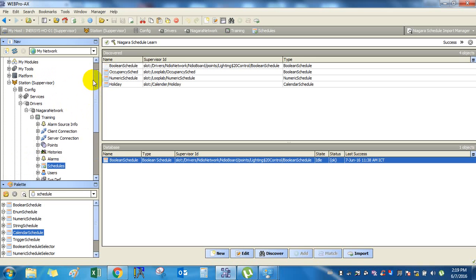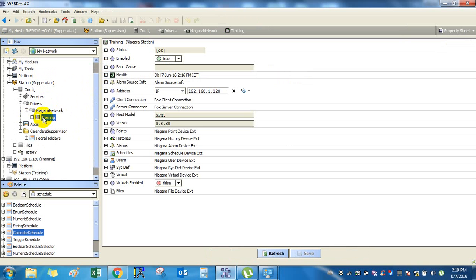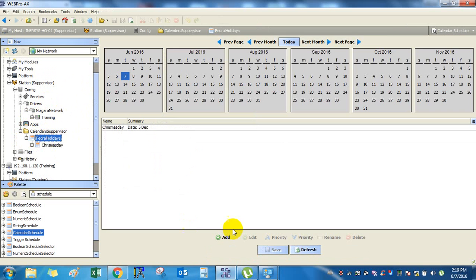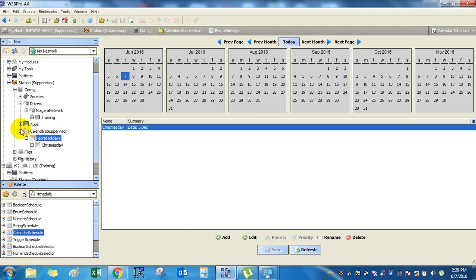So generally schedules don't change very often, right? Do your holidays change very often, every day? No, right? It will change probably once a year. So generally I can keep this trigger mode as manual, and whenever I want to get that schedule, I can just right click and execute it. Or if you want a periodic thing, you can keep daily or interval.